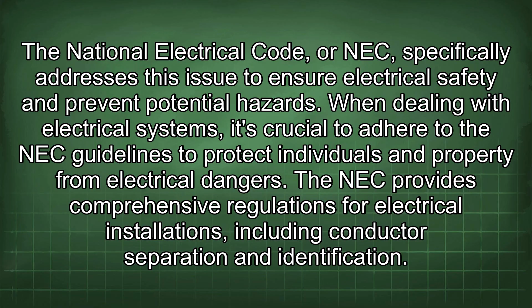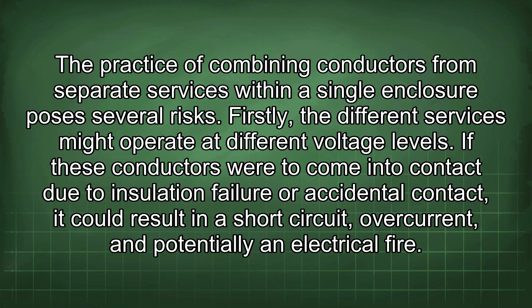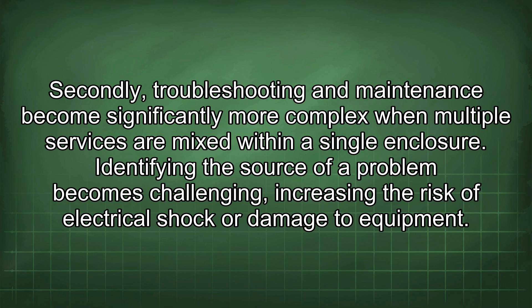Combining conductors from separate services within a single enclosure poses several risks. Firstly, the different services might operate at different voltage levels. If these conductors were to come into contact due to insulation failure or accidental contact, it could result in a short circuit, overcurrent, and potentially an electrical fire. Secondly, troubleshooting and maintenance become significantly more complex when multiple services are mixed within a single enclosure. Identifying the source of a problem becomes challenging, increasing the risk of electrical shock or damage to equipment.